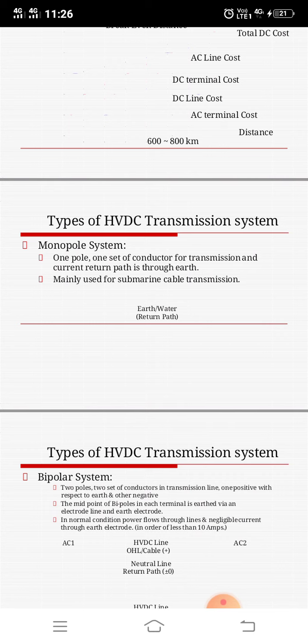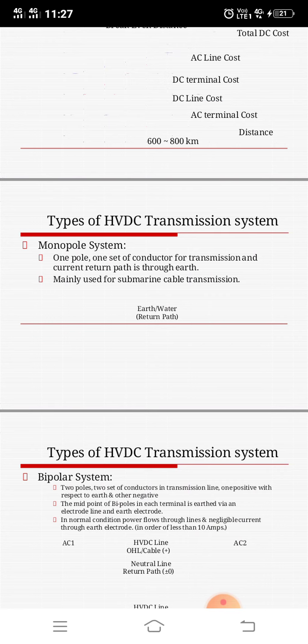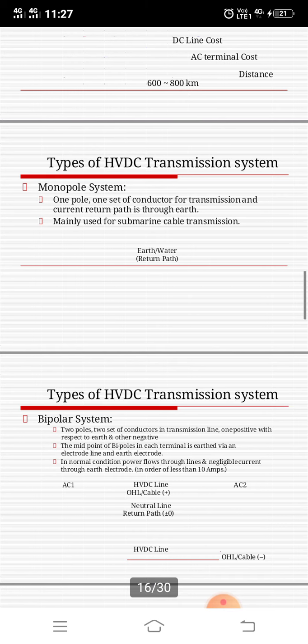Each terminal has two sets of converters of identical ratings in series on the DC side. The junction between the two sets of converters is grounded at one or both ends. Normally both poles operate at equal current, and hence there is zero ground current flowing under these conditions.